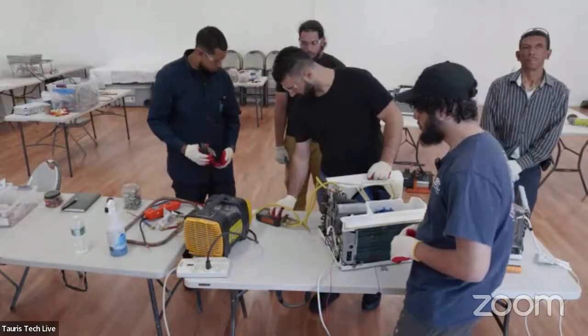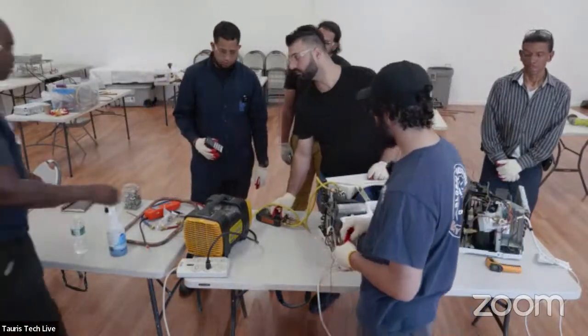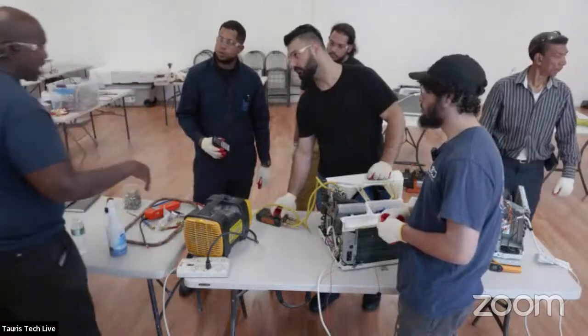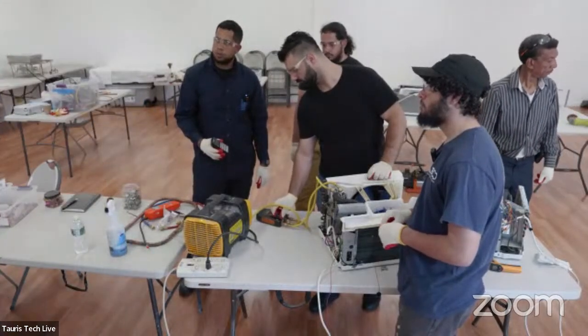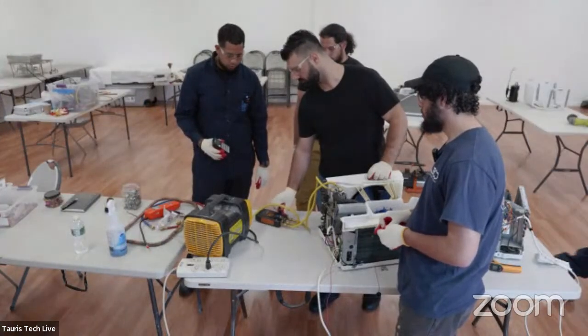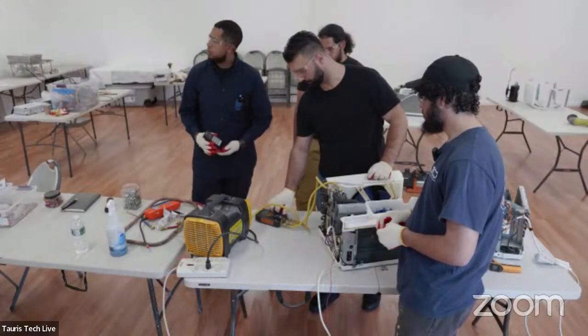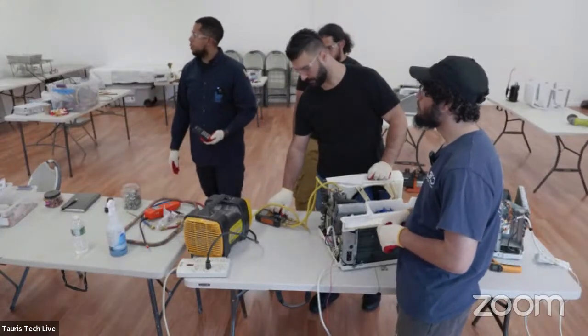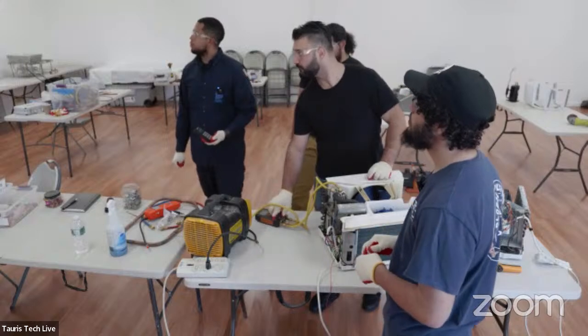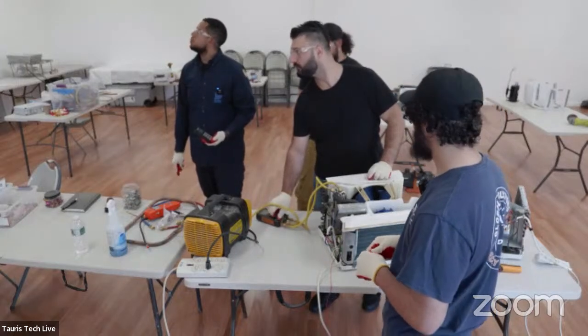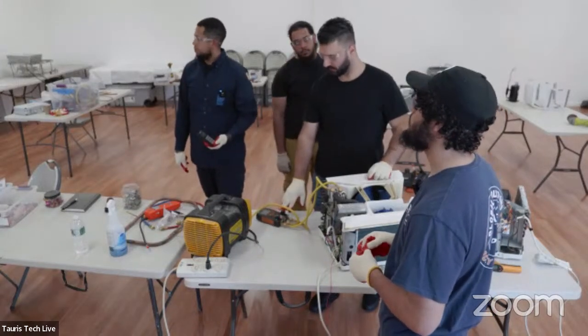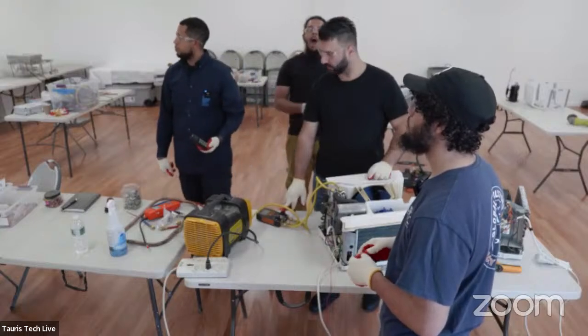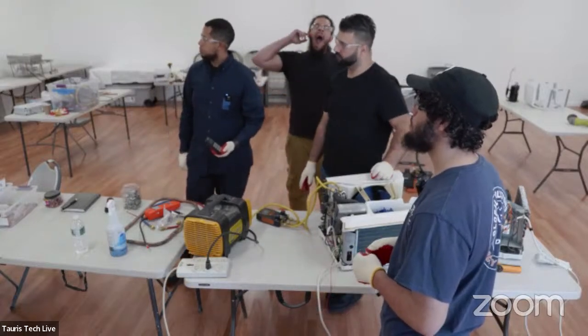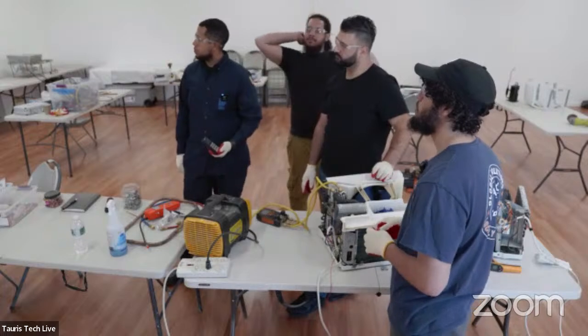Now, how far do we want to go down? You want to go into as deep a vacuum as you can, 10 inches, 15 inches. Just let it run until you go deep. Is the ideal 29 or 29.95, if you can get that? We already know those valves are leaking, so you're not going to get that. Sometimes you can only get to 0, but you just want to make sure you recover until it goes as low as it can go. You have the majority of the refrigerant out.